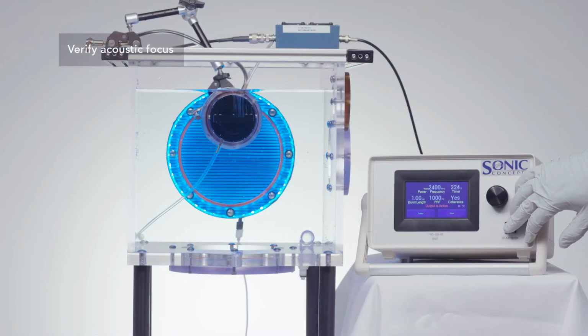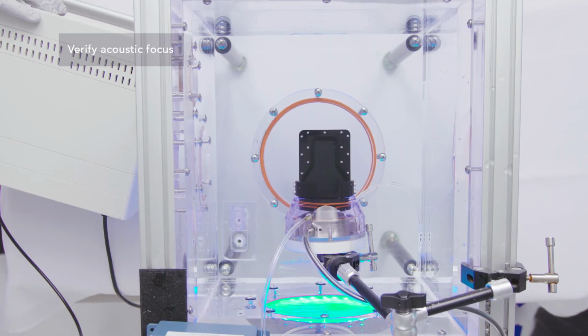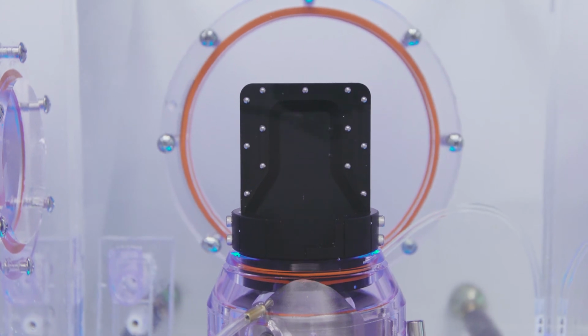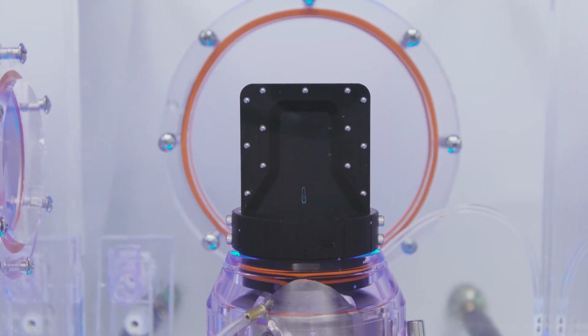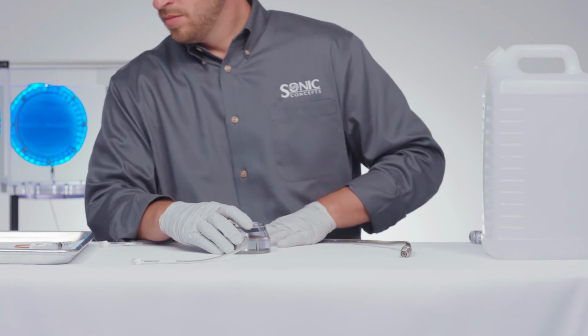Using the operating conditions as set forth in the calibration report, verify that the transducer is focusing appropriately. Once the focus is verified, remove the target assembly and prepare to install the coupling membrane.